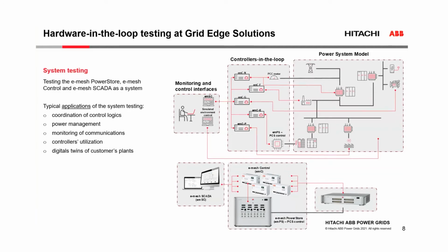And then we also add the e-mesh SCADA. With this test setup, we are able to verify the coordination of our control logics running on different hardware and at different speeds. We can also verify the power management made by the e-mesh Control, and test and verify the communications between all these control systems, because in a system like this with distributed controllers, communications play a key role.